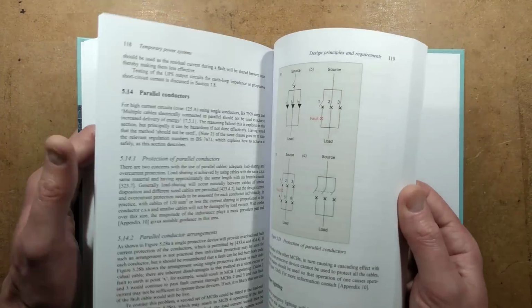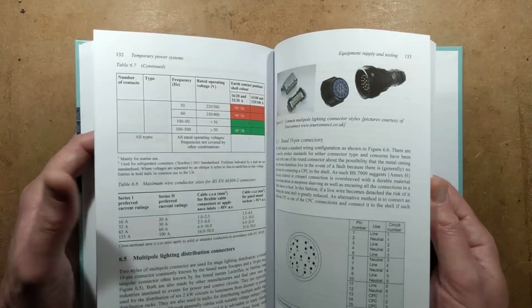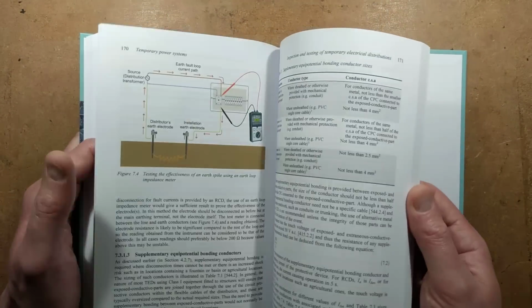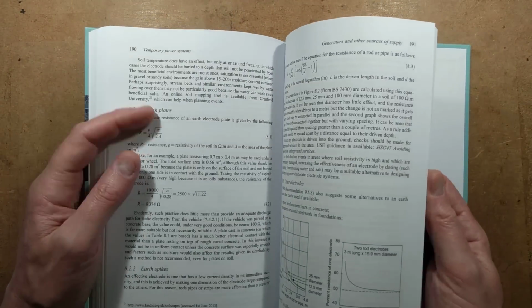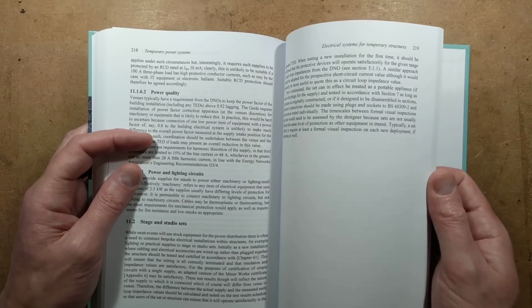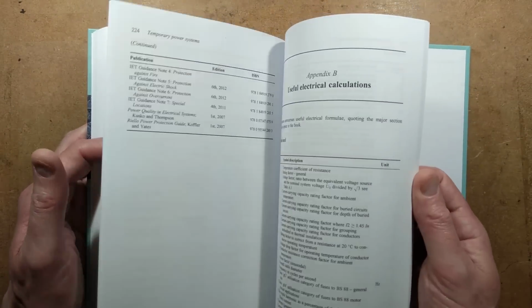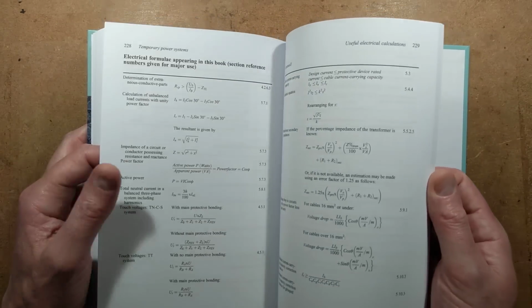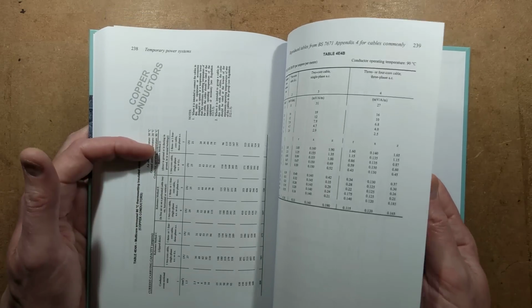It covers harmonics, it covers protection, connectors, testing ground electrodes, the best arrangement of ground electrodes, why sticking an earth electrode under the tyre of a generator is completely unacceptable, and lying it flat in the ground is also unacceptable. It's got charts for copper conductor sizes, current ratings, protection, and trip curves of circuit breakers.